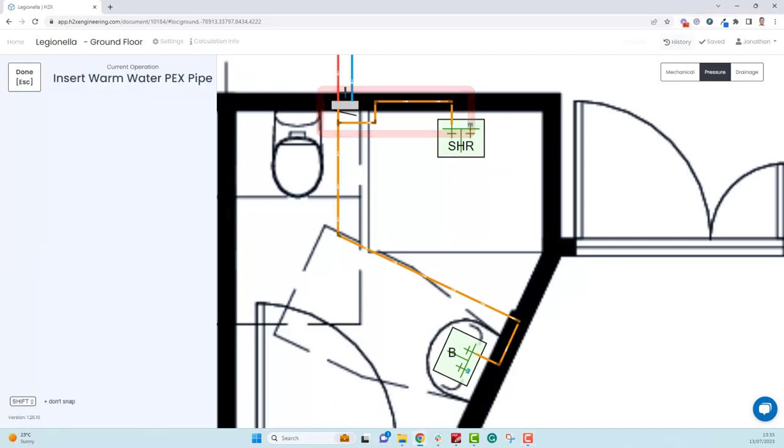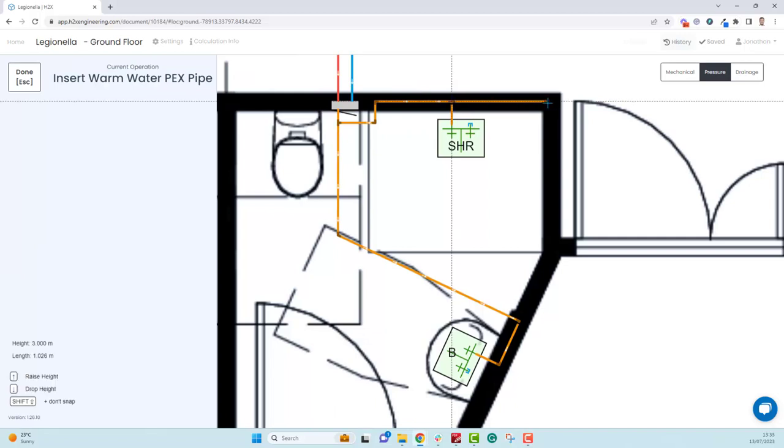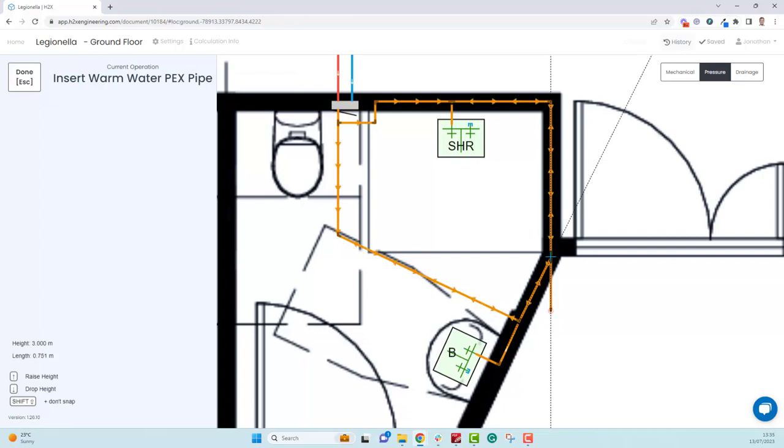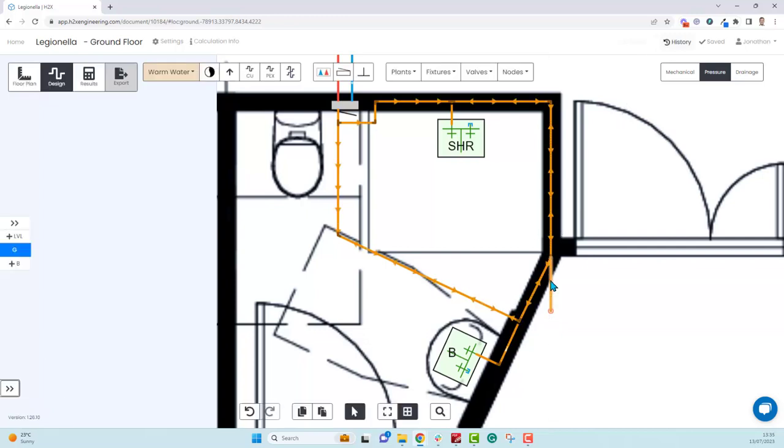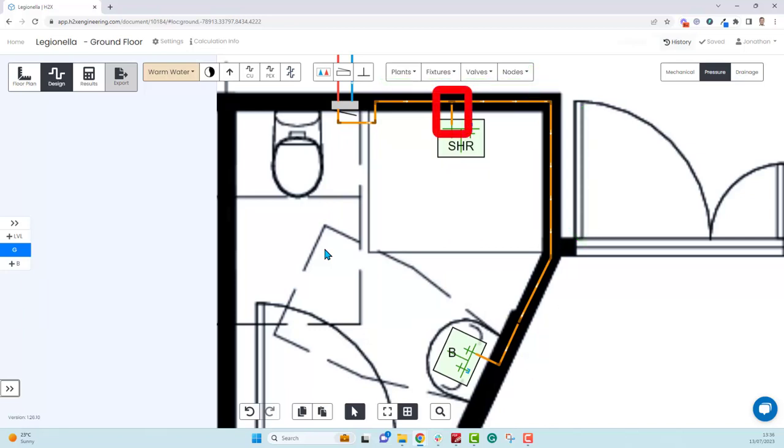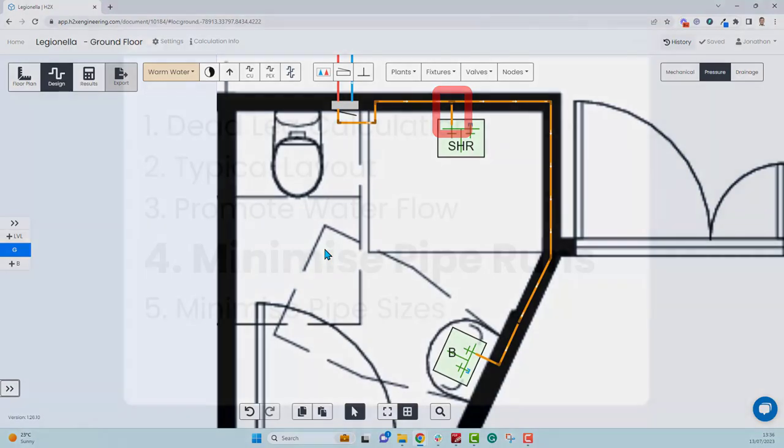An improved layout would be to connect the basin downstream of the shower. What this means is that every time the basin is used, it's going to flush much more of the dead leg, and the remaining dead leg that's connected to the shower is minimized significantly.